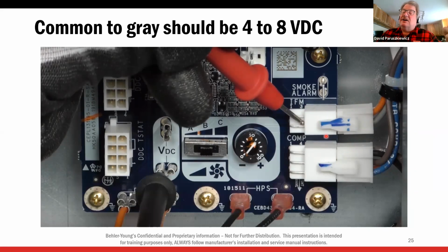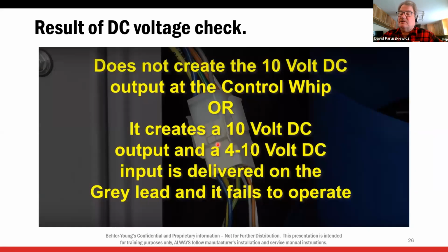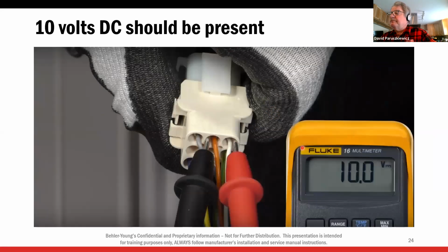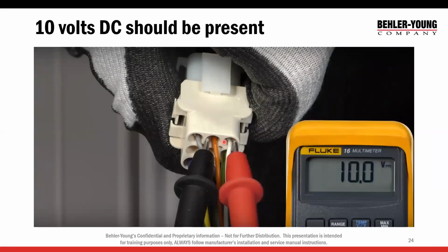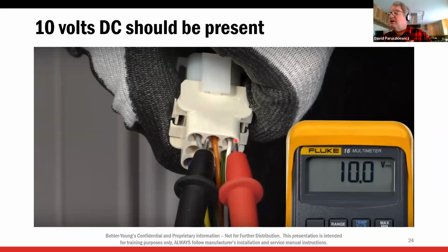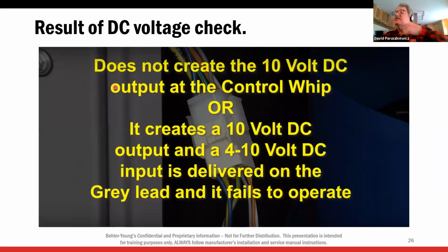Now, on a call for blower, again, it sends that 9 volts we created back down the gray wire. So then I can go back to gray to white here, and I should have 9 volts if the blower is being called for. So again, does the motor create the 10 volt DC, orange to white? If it does, then we check our output on the call. So when we set that 9 volts DC, we're calling for the blower, we should have 9 volts going back.